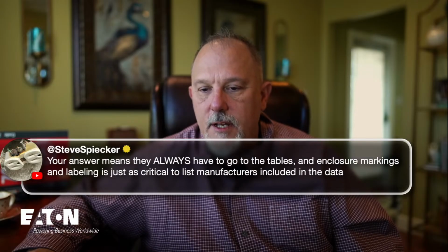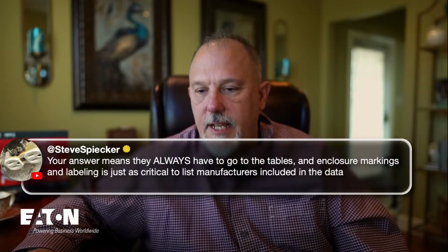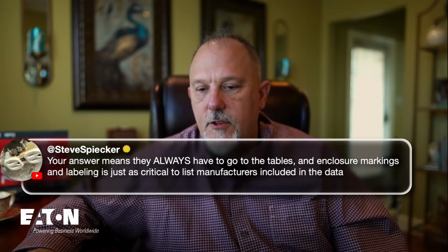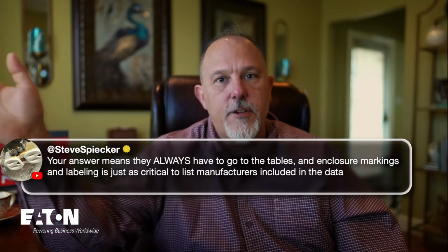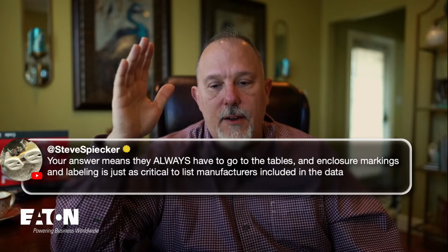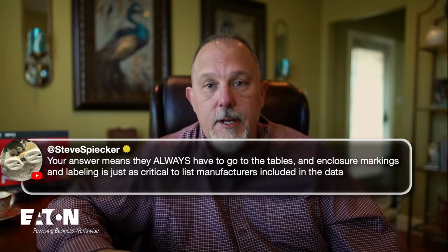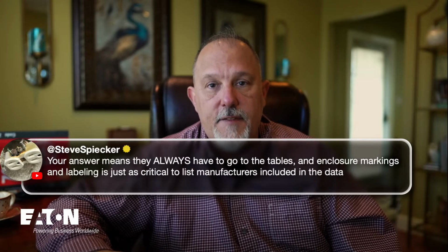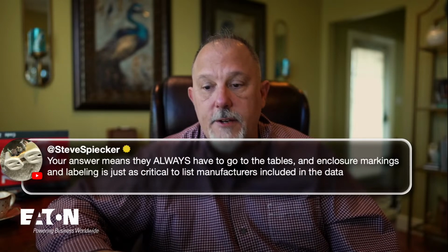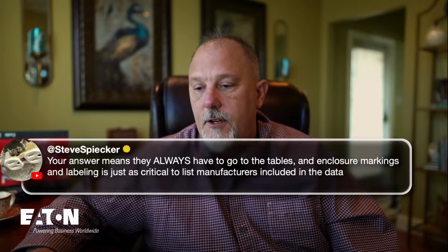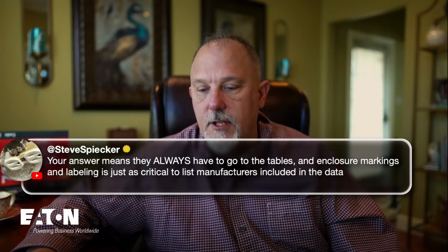Your answer means they always have to go to the tables, and labeling is just critical. Only if the fault currents are high enough. Okay, and Steve, I would argue, I agree with you. The fault currents are typically high enough; they're in the instantaneous region of most of these breakers. So you're gonna be using those tables a lot.